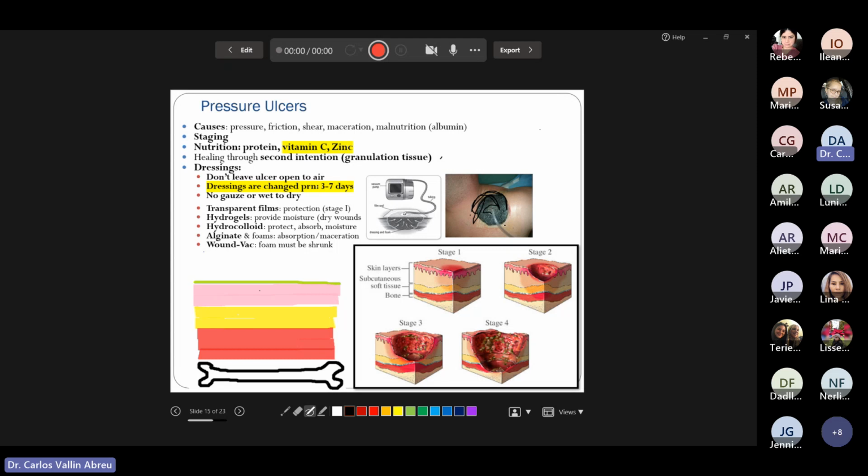This foam, because it's under suction, under negative pressure, should be flat, or even sunken. If it is bulging, it means that the vacuum, the negative pressure, has been lost. For that reason, it's bulging.